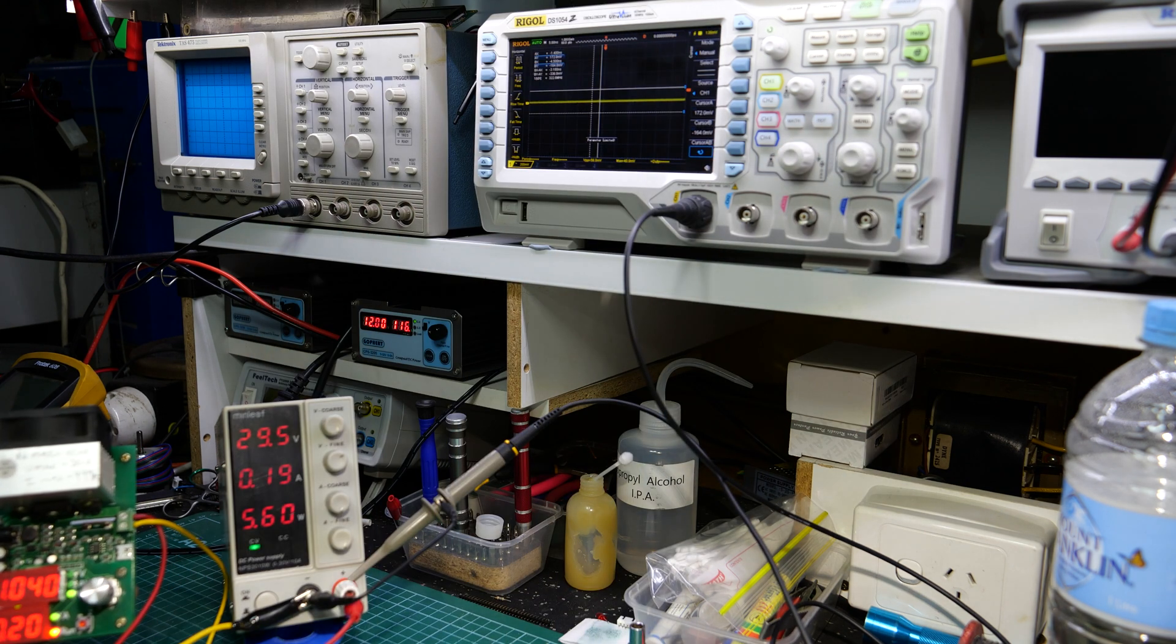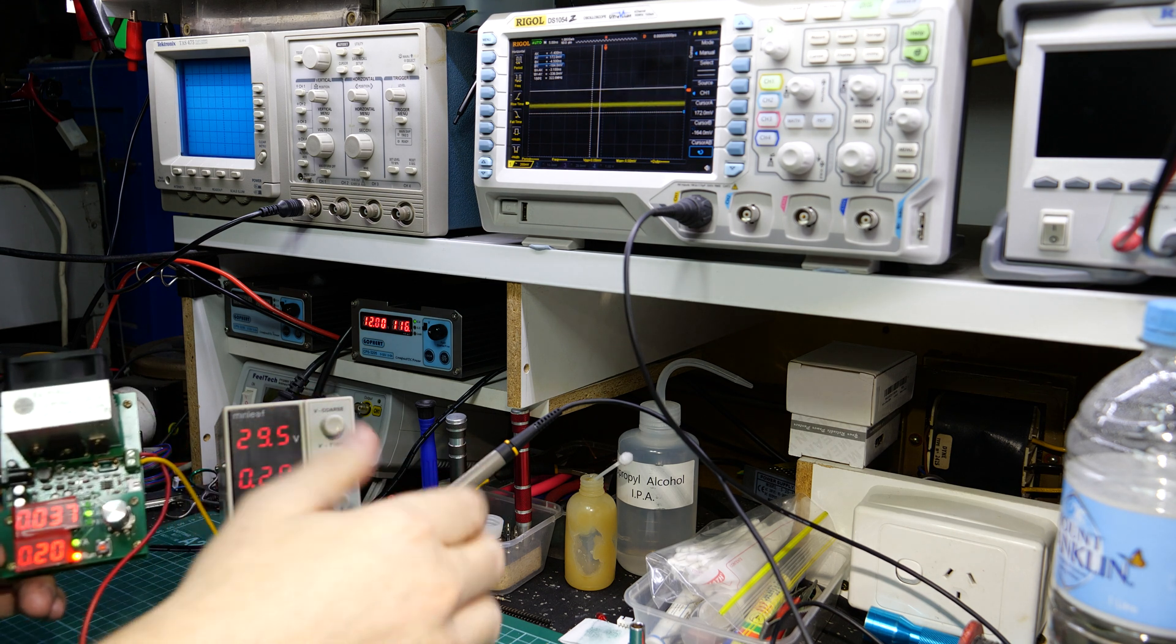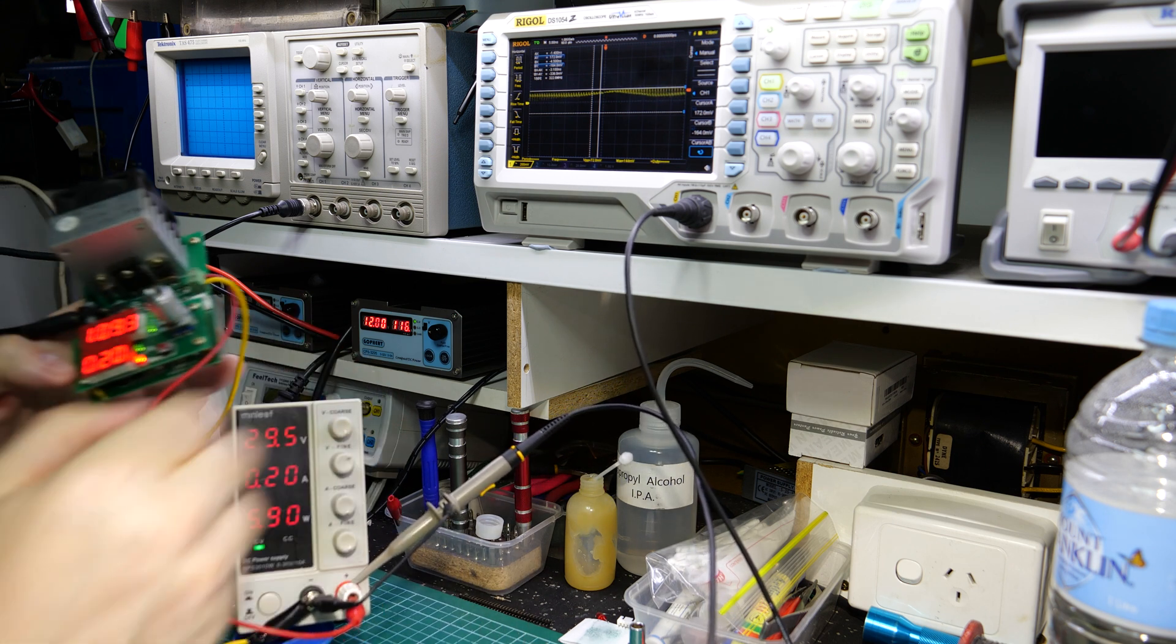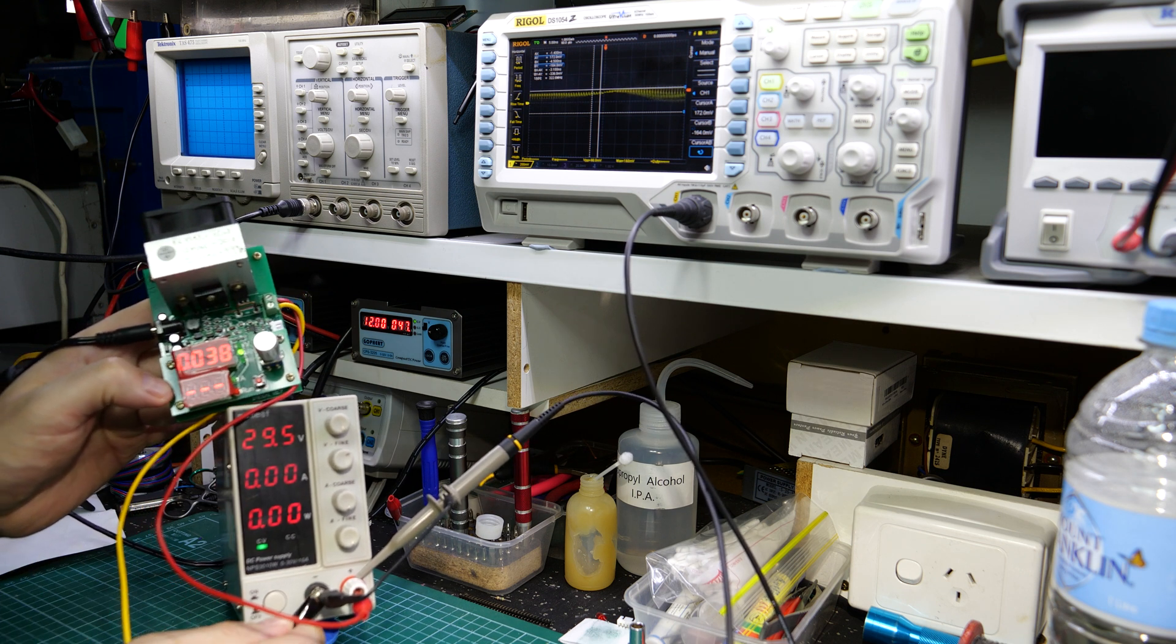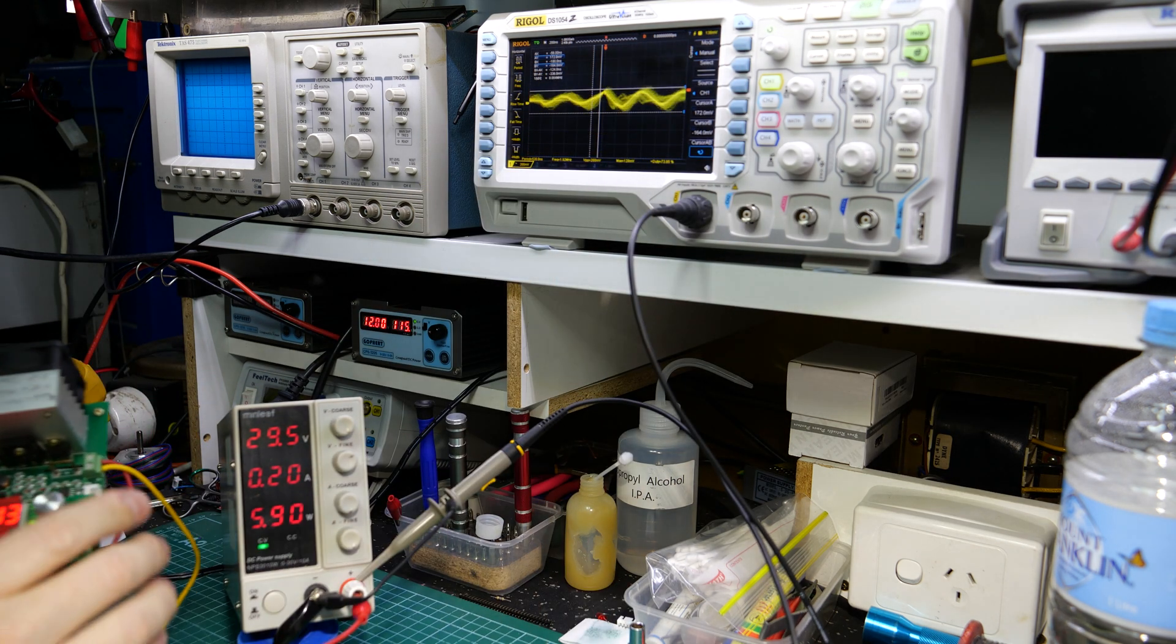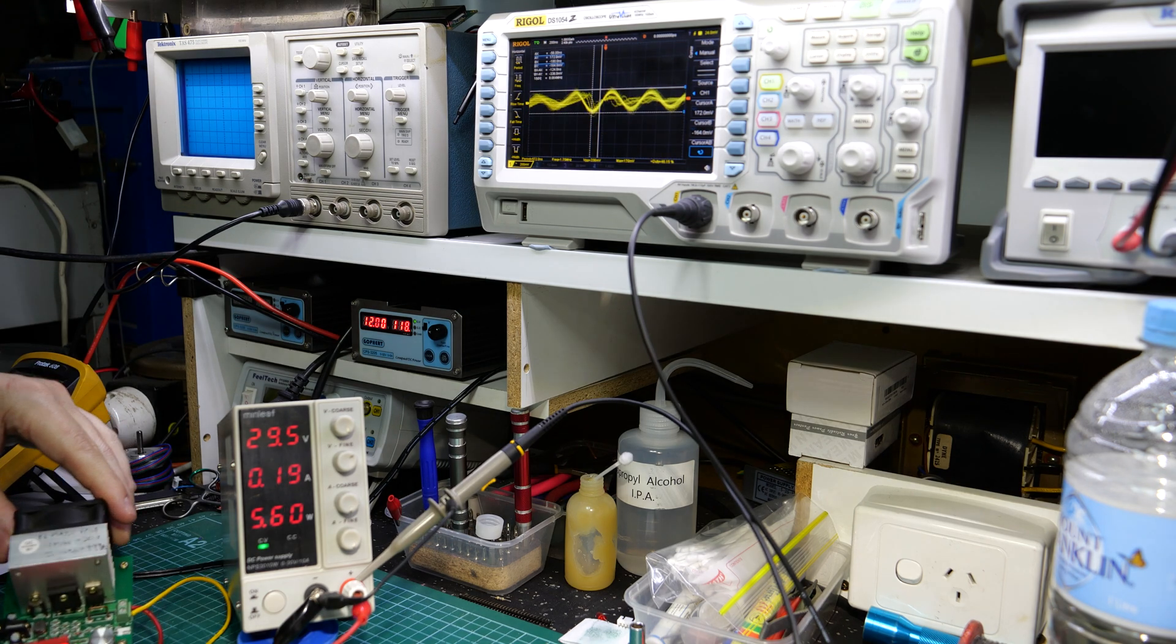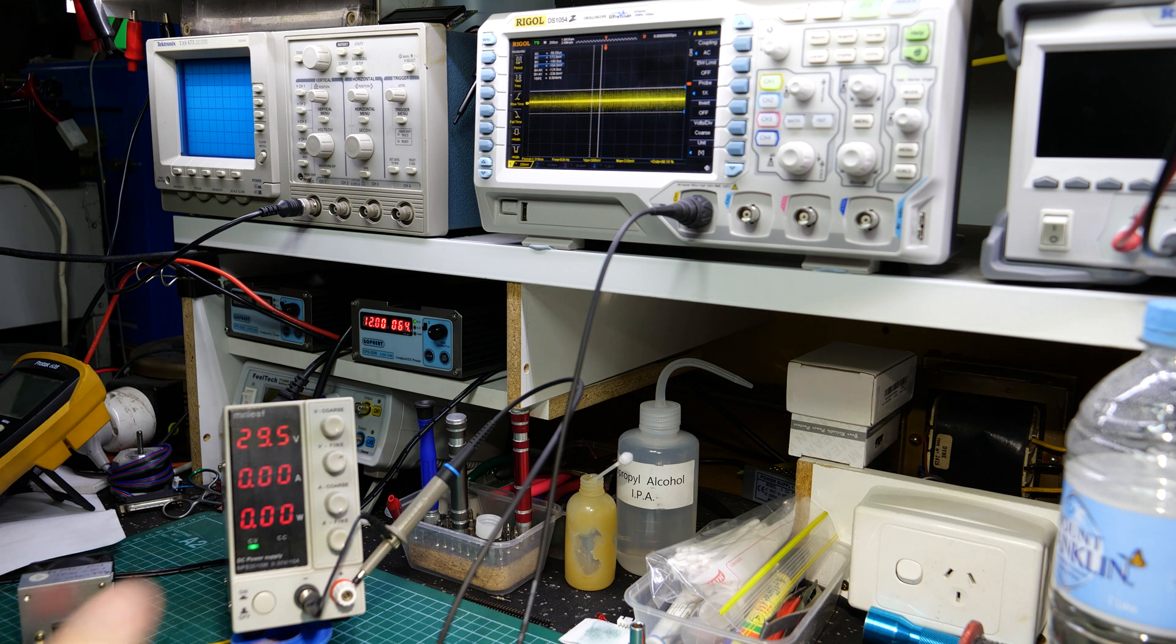We'll leave it at that. That's really odd, look at that. Why is it doing that? It sort of comes good like it is now. That's now reporting 40 millivolts, 40 to 56. No way. Let's crank up. What's it doing? Is this an issue with my gear? No, my leads aren't making any difference. Do we have a crook joint somewhere? No, okay, something's not right. I'm going to change my probe, change the probe out and see if that sorts the issue out. That's pretty bad. That's jumping around all over the shop. I'm not happy with that. Changing the probe out, be back shortly.